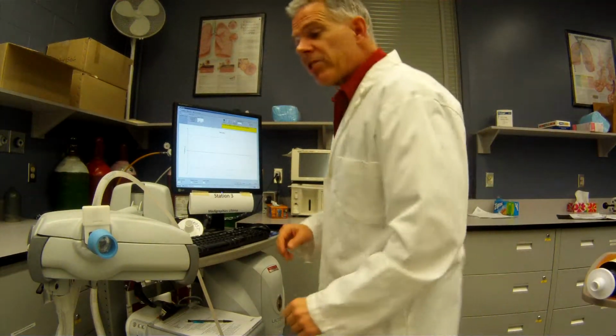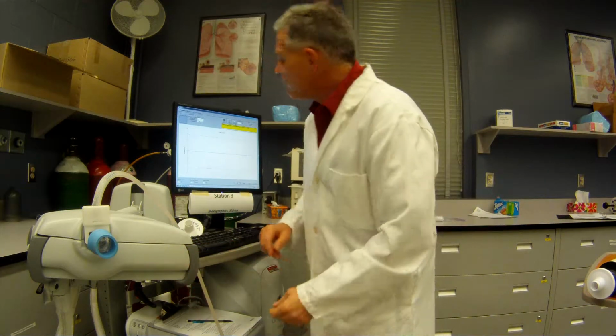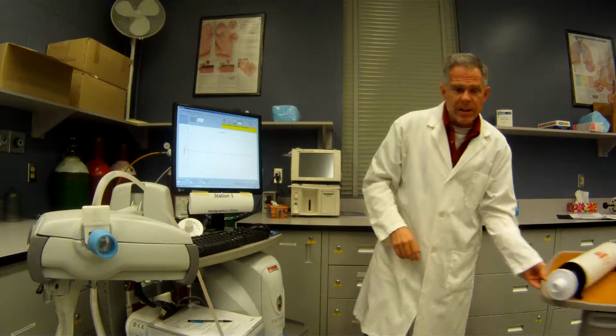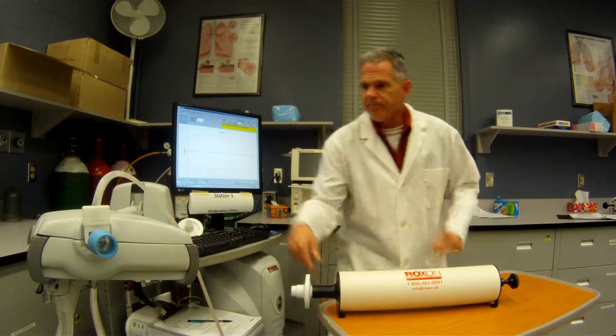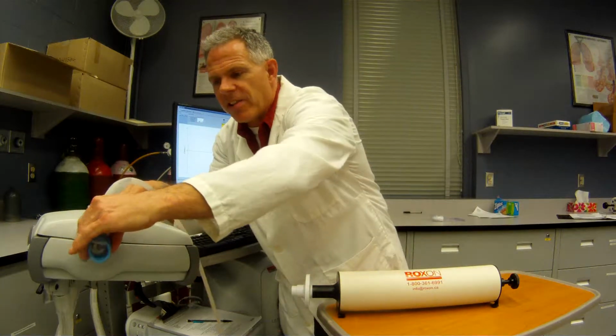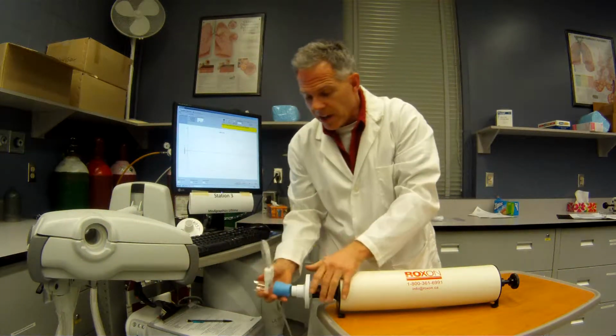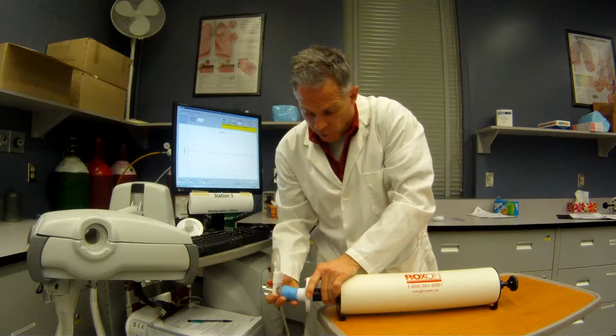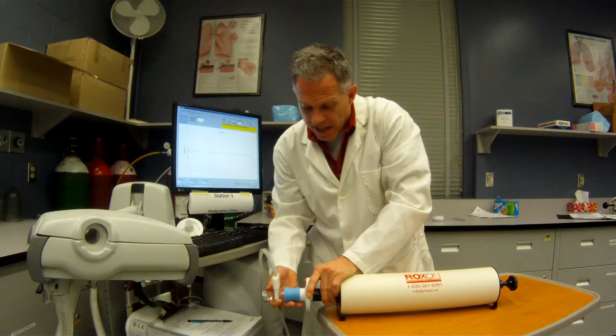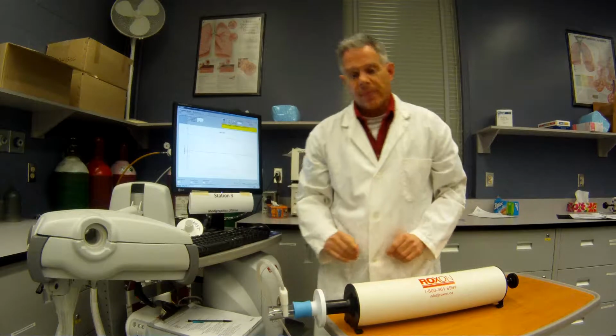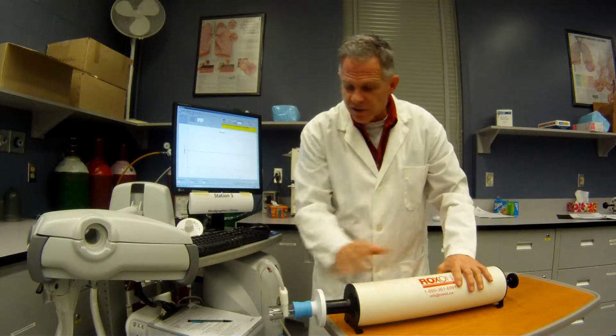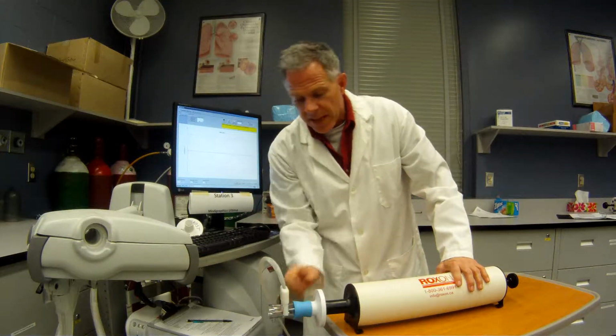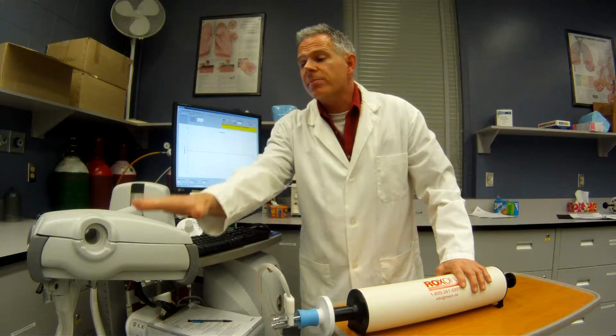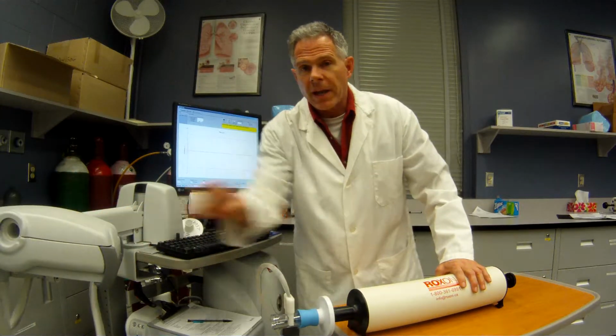All right, so we're going to be calibrating this pneumotach. So I need a 3-liter syringe, and I'm going to just take this off of here. So this can be done anywhere. We're going to do this every single day before the device is used. Okay? So I've got my 3-liter syringe, I've got my pneumotach hooked up to the end, and I've got a filter here just mimicking like we would have with our patient on here.